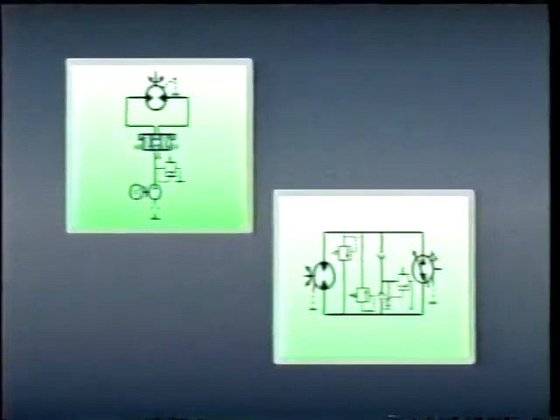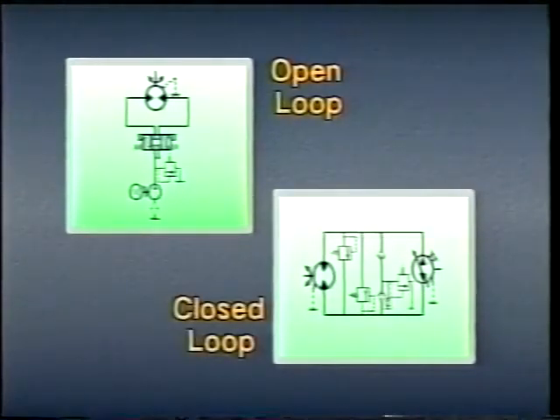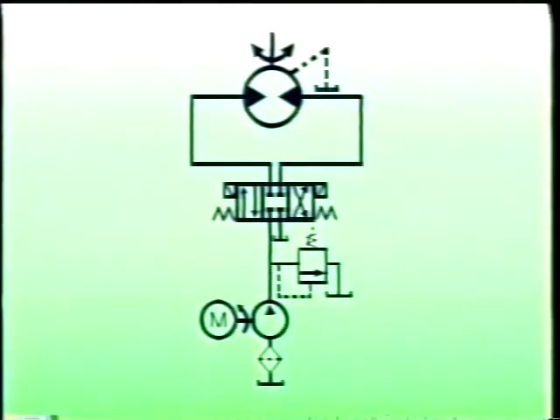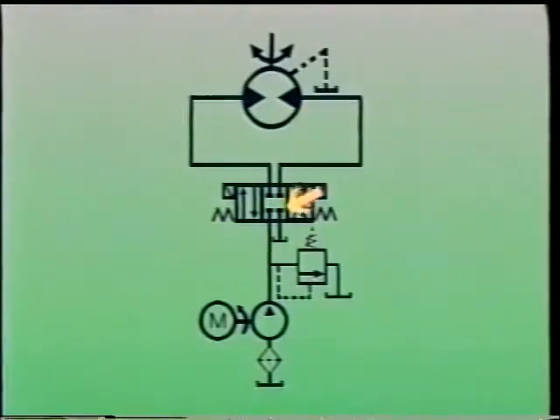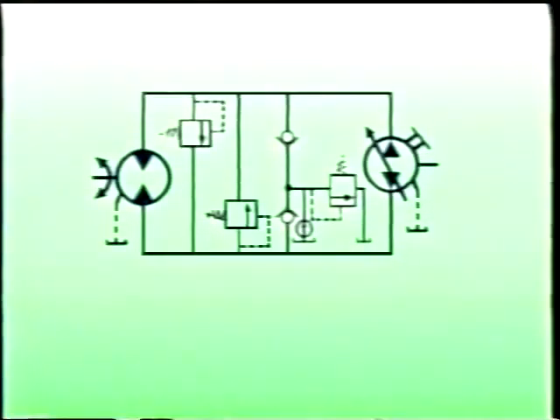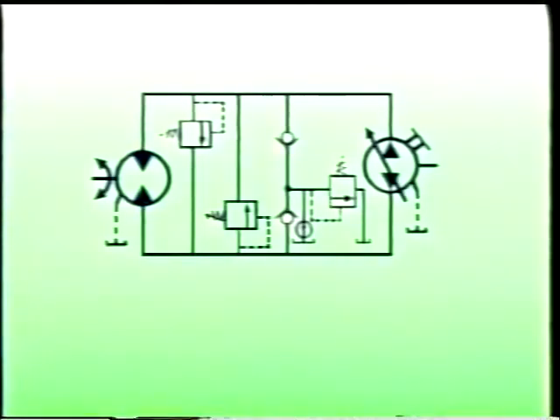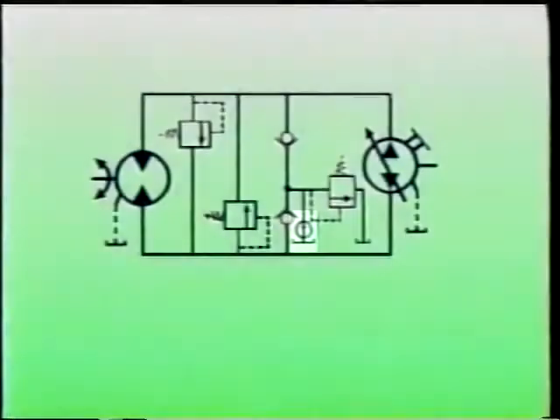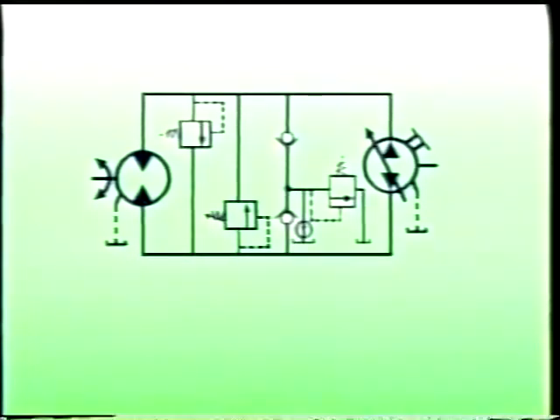Hydrostatic drives and hydrostatic transmissions can be either open loop or closed loop depending on how they are configured. An open loop system has the motor inlet connected to the pump outlet and the motor outlet connected to tank. In a closed loop, the motor outlet is connected back to the pump inlet, forming the closed loop. Any fluid leakage in a closed loop is made up by a replenishing pump. Since most of the fluid in closed loop drives and transmissions is carried in the system piping, only a small reservoir is required, allowing closed loop drives and transmissions to be very compact.